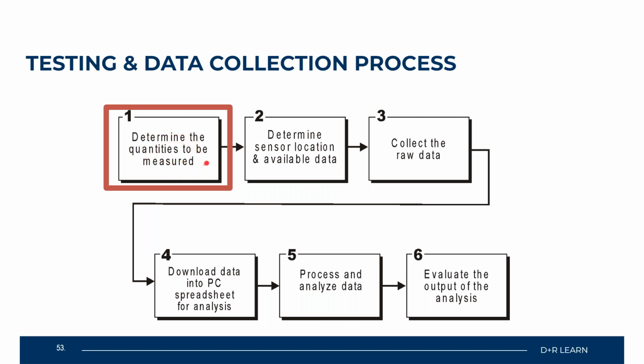So you have the sensor, you know what it does. Let's say you're looking for a temperature sensor. Where in this system are you trying to put it? Are you trying to put it at the supply point where we are measuring the actual air blowing directly across that cooling coil? Or are we trying to measure it at the actual room or zone or site or office where we have the occupant trying to get either cooling or heating to feel more comfortable, right? So with these different sensors, you have to figure out where you're trying to read or collect this data so you can make your diagnosis or whatever it is that you are looking for as far as why you're putting that sensor in that location.